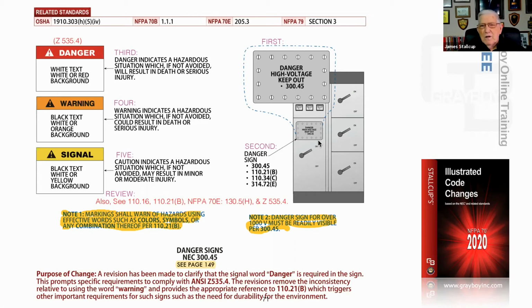So again, we could have this main here. This instrumentation now has to have its own barrier so I can get in there and do things, not be exposed down here. We know that 70E allows that. And then here we could have a barrier, and we'd have those mains - 230.71(b), 1 through 4. So we picked that up.